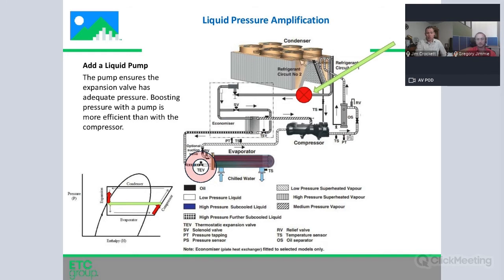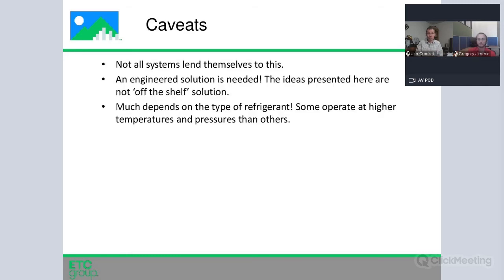So if you can run your condenser a little colder, that allows your compressor to not work as hard, and it transfers potentially some of that work to a liquid pump where it does it more effectively, and that gives you enough push to get through the expansion valve. Not all systems lend themselves to this. This is dependent on the type of refrigerant that you have in your system. It's not an off-the-shelf solution. Some chillers just aren't good candidates. If you've got like a flooded type system, it may not be a good candidate.